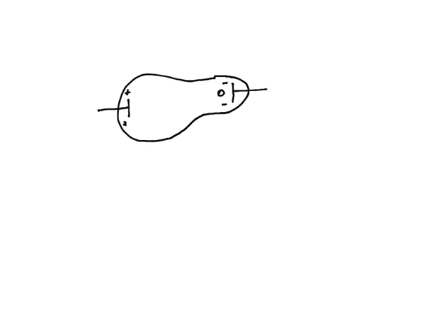And that way, when an electron is sent, it's sent directly towards it, and so every single electron will hit. And in fact, that was the first evolution. They moved the anode to be directly across from the cathode, and thus much more efficient at producing X-rays.